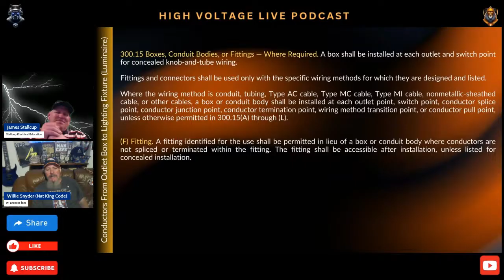So go back to that picture again, James, the Myth of the Week picture. Yeah, so per code, this is a violation. You have a PVC male adapter that's listed for rigid fittings, and a rigid coupling that's going on there. That's listed, so technically two parts of it are listed, but the EMT connector is not listed to thread into anything. The EMT connector is only listed to be used with a lock ring. So there's no way you can make this a listed transition fitting.